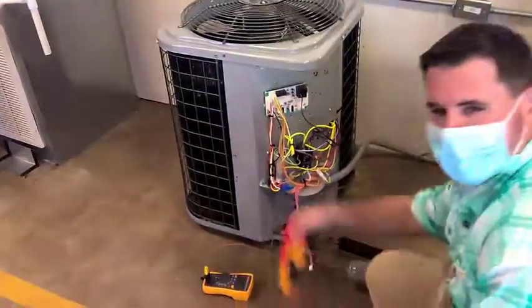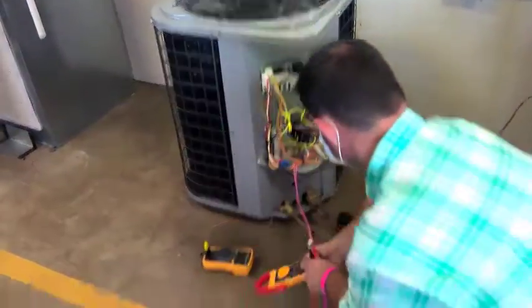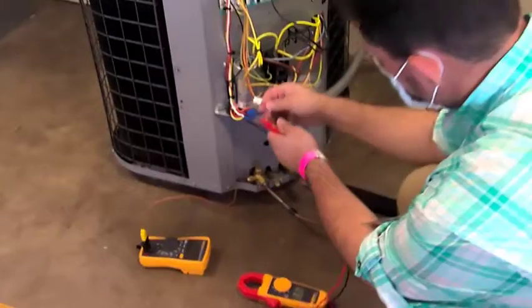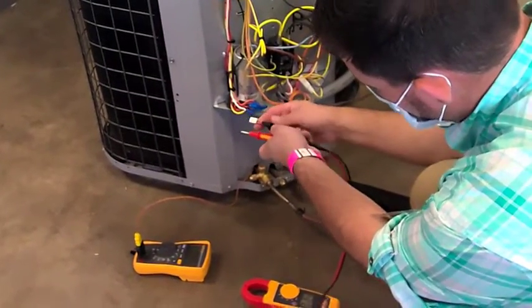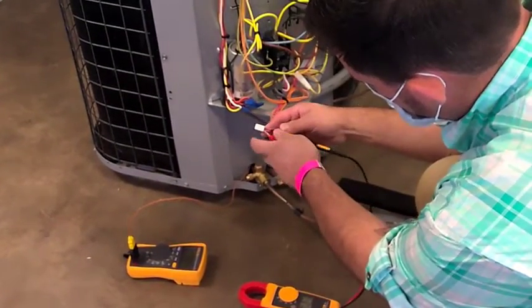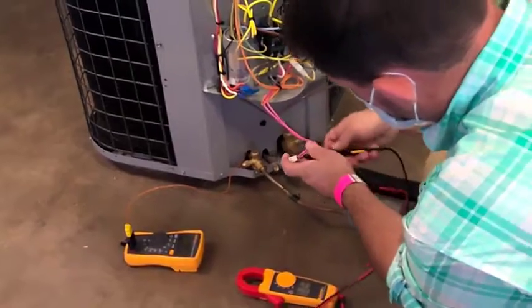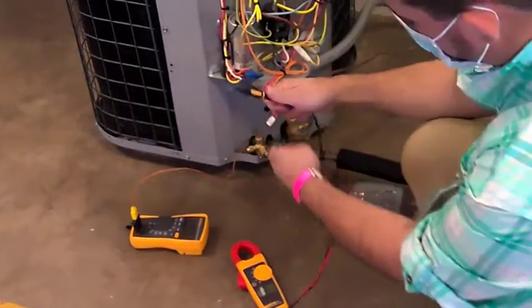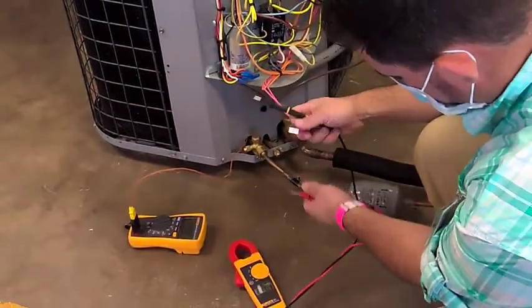So I've got my meter set to ohms. I'm going to insert it into the back of the coil sensor to see what temperature we close at. Check it first and make sure that the meter's working right.